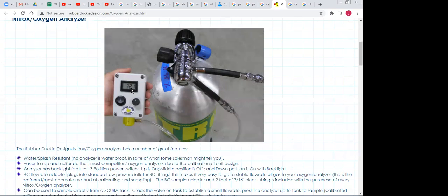For other operations like inerting, we need less than 5% oxygen. There are so many places and operations where we need to monitor oxygen — that's why we need oxygen analyzers. Mostly we have portable oxygen analyzers, and there are different types: zirconia-based, paramagnetic, and electrochemical cell.